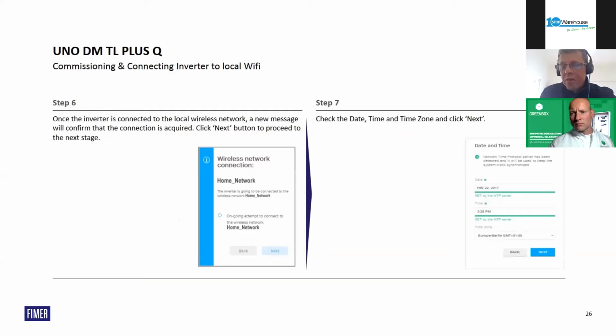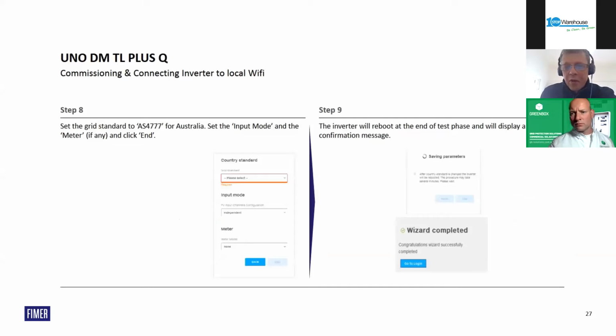Next is just setting time and date. This is usually pulled off the phone or the tablet or the PC. Then setting the country code. In Australia, it's AS4777. For the input mode, you can set it to independent if you're using two independent MPPTs, or if you choose to parallel the inverter, you can select parallel also after you install the paralleling links inside the inverter. Connecting a meter is super simple, just a drop box. The standard energy meter that we supply is the B21 meter or the B23 meter, depending on the size of the consumer mains. They'll be available in the drop box, and just connect to that and you're away. That's how simple it is.